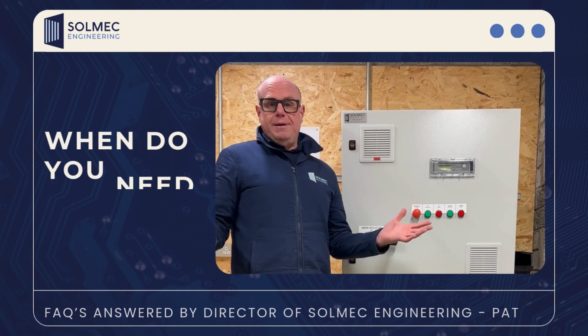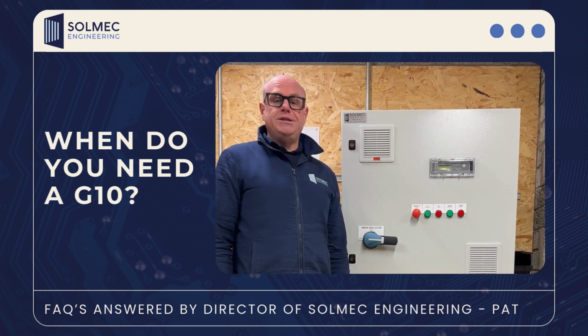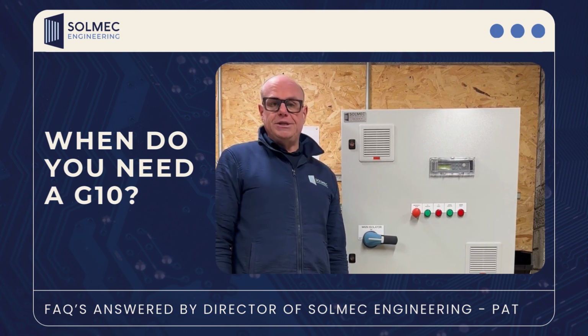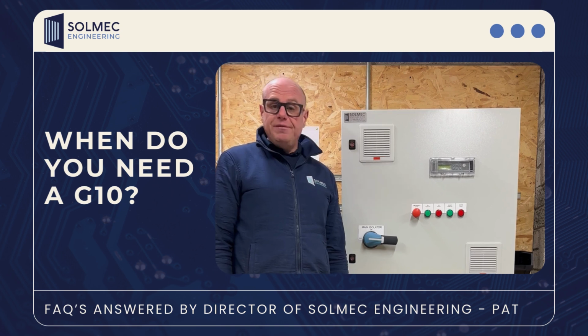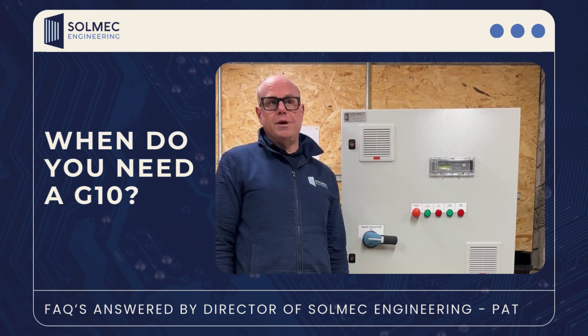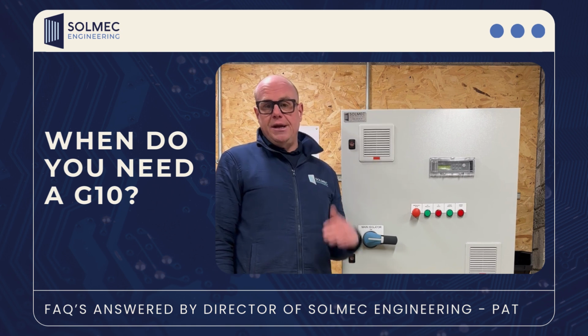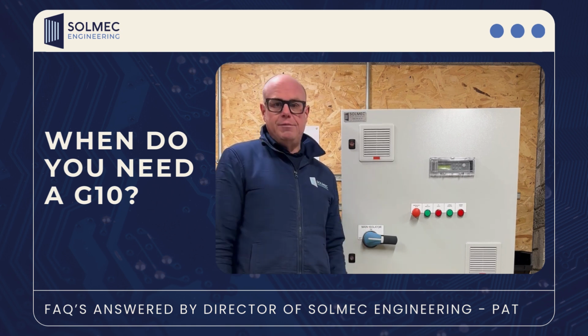The first question a lot of people ask is, when do you need the G10? You need the G10 when you go into small scale generation and above. This is usually at 50 kilowatts, up to 200 kilowatts is small scale generation. Then you can go above that, but that's a different kind of ball game, which I'll talk to you about in another video.